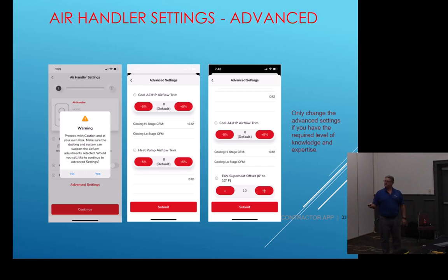And the reason why is you can come in here and change this airflow setting 10% here, 10% here, 10% here, and we can change this airflow up to 30%. So we can increase it or decrease it. So let's say we have a 3-ton, 1,200 CFM, roundabout speaking, right? If we reduce it 30%, we're looking at what? 900 CFM, maybe? Is that good for a 3-ton? Probably not, huh? So when it asks you, it's asking if you really know what you're doing.